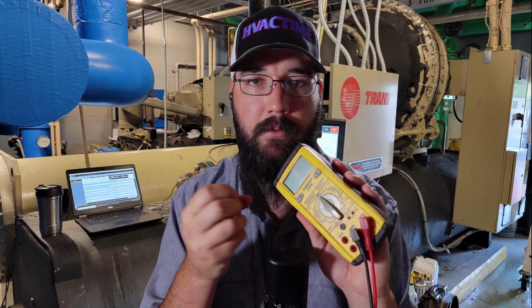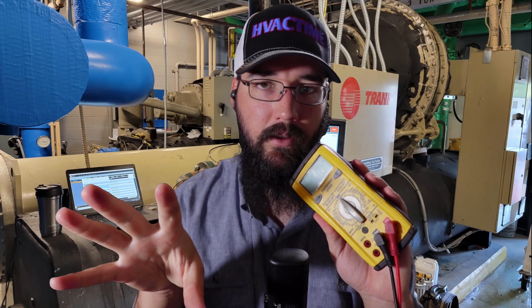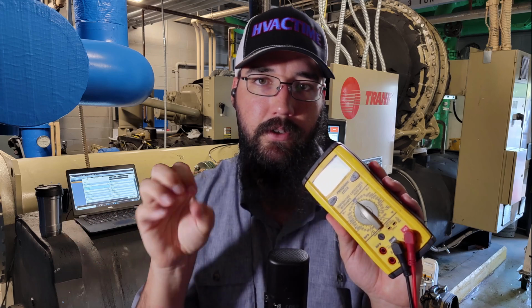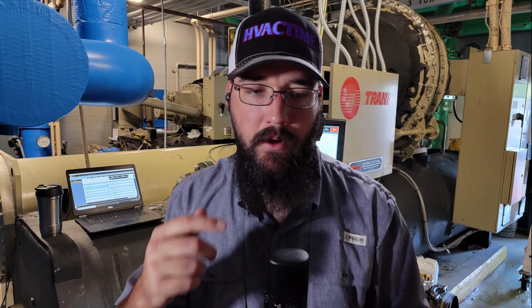What I mean by pulsing is your reading on your display is going to just flash back and forth from 0 to giving you a voltage, 0 to giving you a voltage, and it's going to do that continuously. And that is that pulsing action. Every time that pulse happens on your meter, it's taking a step. Now, there are some meters that have algorithms built into their reading to help smooth that out. And so you may have some meters on the market that you'll take that reading and it may look stable on your meter. In reality, that's the meter just taking that pulsing signal and giving you a consistent display. It's not what's actually happening at the valve level.